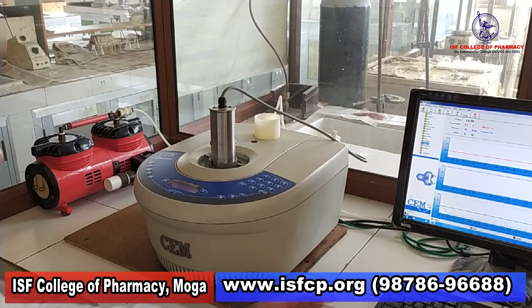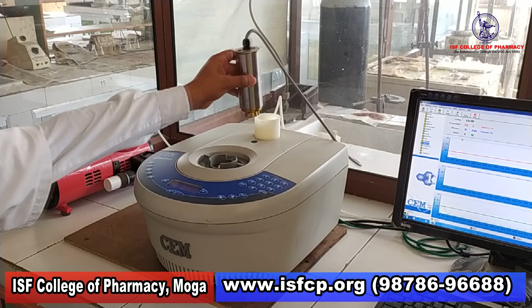So our time set for this reaction is over. Now microwave is automatically cooling the reaction, and it will only release our reaction vial when the temperature is below 50 degrees Celsius. As the temperature reaches 50 degrees Celsius, the pressure control device will release the pressure. So now it is safe to remove the reaction vial from microwave assembly.